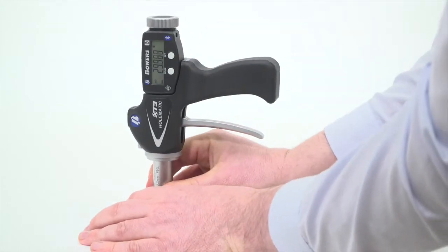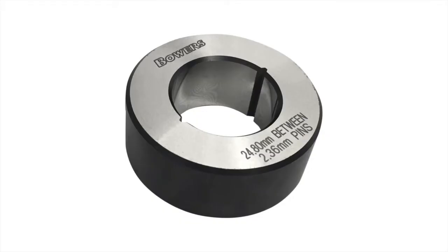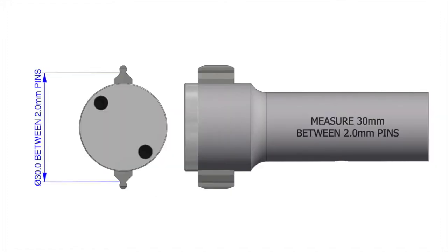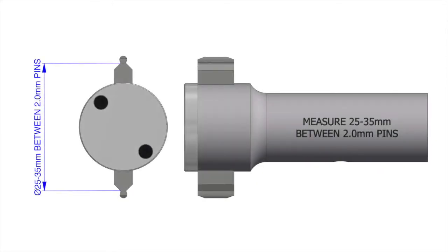The gauge can be calibrated in a plain ring, or for the very best accuracy, a two-space master ring. Heads can be custom made for a specific spline or gear size, or can be supplied with a specified measuring range to cover a family of common tooth sizes.